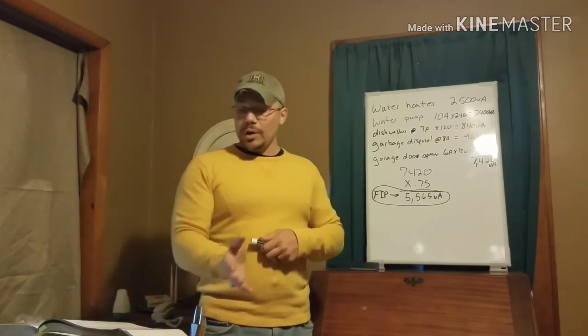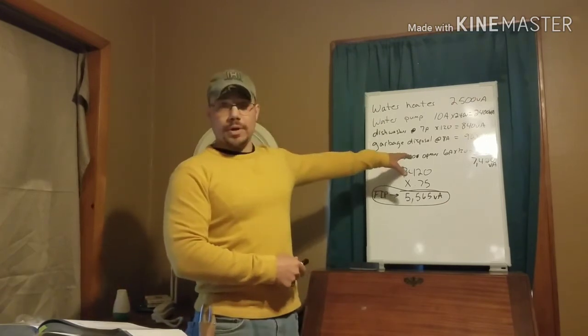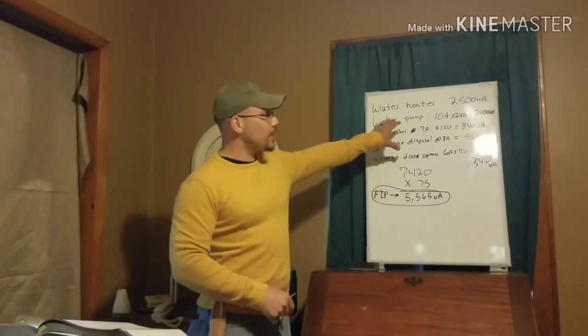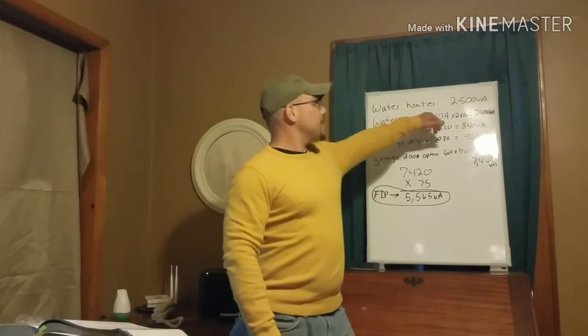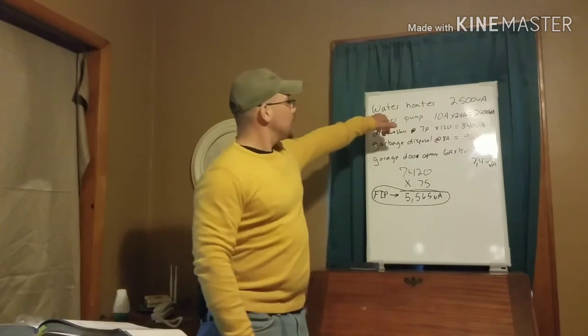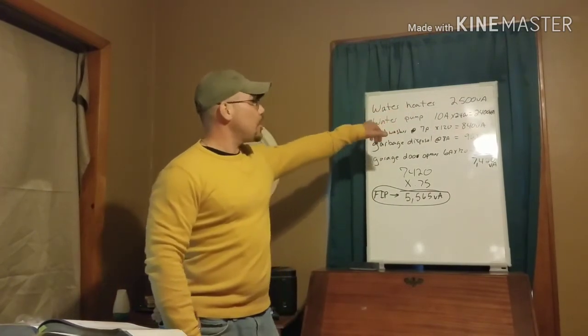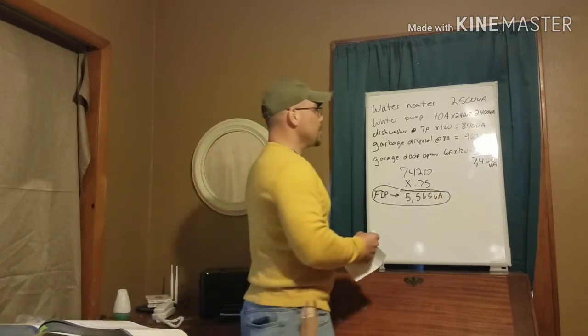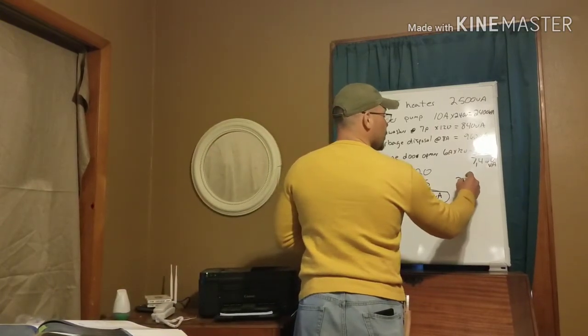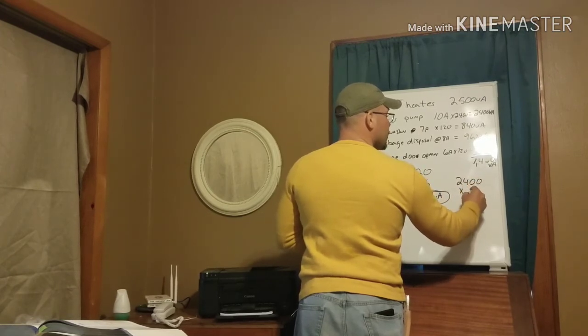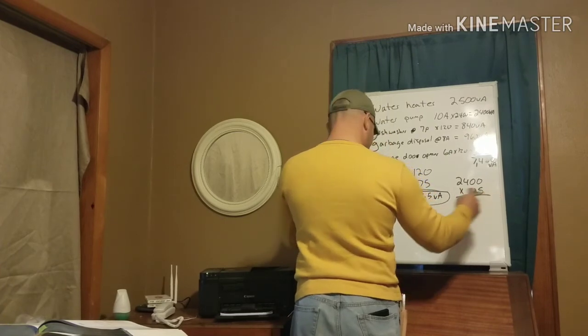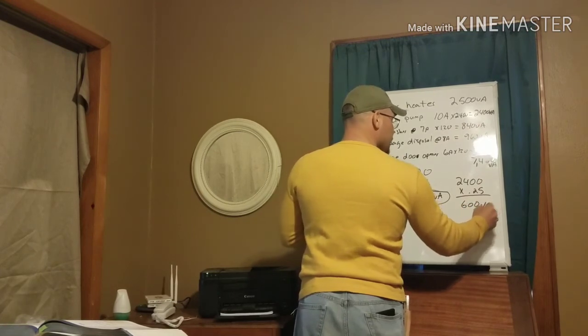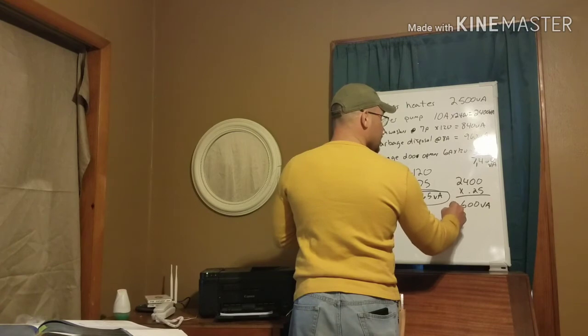The other items in 430.24 have already been incorporated in our calculation. The only thing we haven't accounted for is that 125 percent of the full-load rating of the highest-rated motor — we've already included the first 100 percent with our small appliance loads, so we just need the extra 25 percent. Among our fastened-in-place appliances, the water heater is not a motor, so the highest motor is the water pump at 2,400 VA. We take 2,400 VA times 25 percent, which gives us 600 VA as our largest motor load.